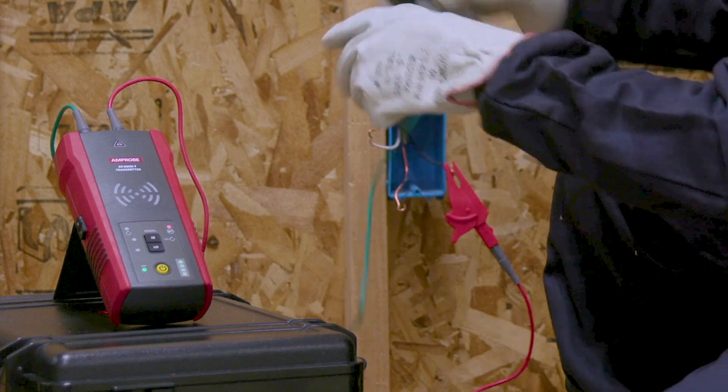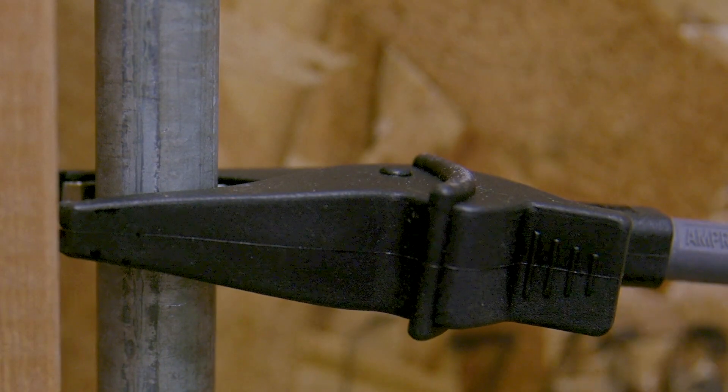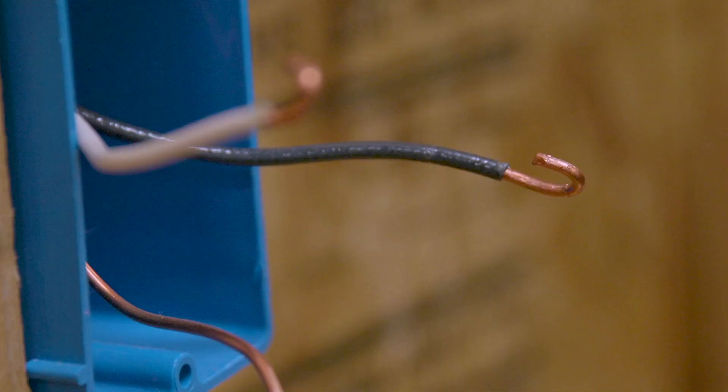Connect the green lead to a separate ground to avoid signal coupling. The red LED indicates proper connection of the test leads to the energized line. Push the high button to induce the tracing signal.